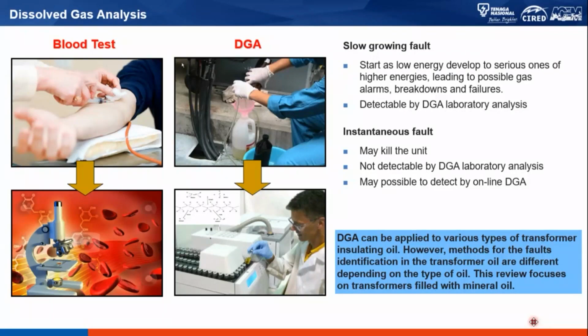I mentioned mineral oil as the focus of this presentation, but I want you to realize DGA is not only for mineral oil. It can also be performed and interpreted for other types of oil, such as ester liquid, synthetic ester, or silicone-based oil. There are standards governing DGA for these other oil types too, even though we're talking mostly about mineral oil, since a lot of transformers still use mineral oil as their insulation and cooling system.